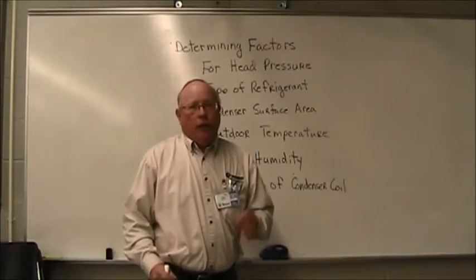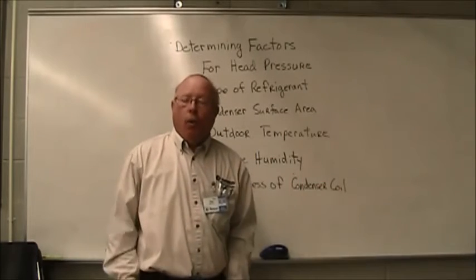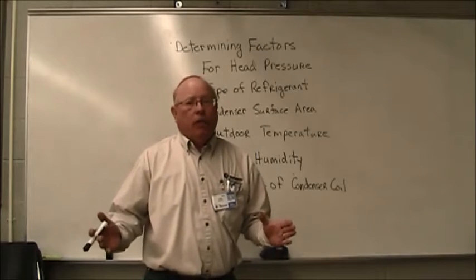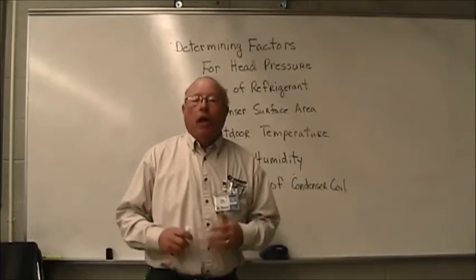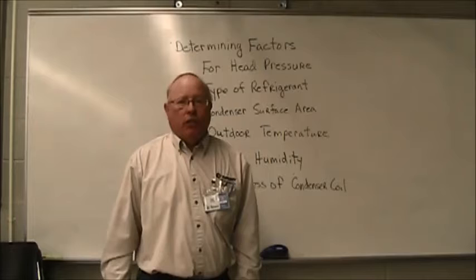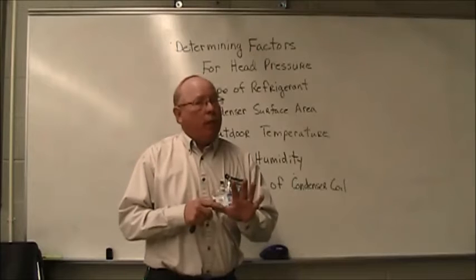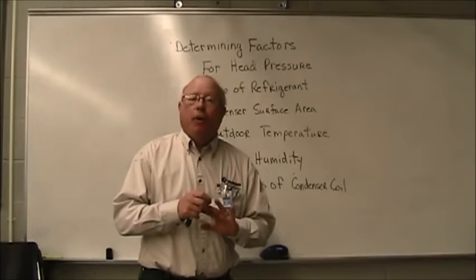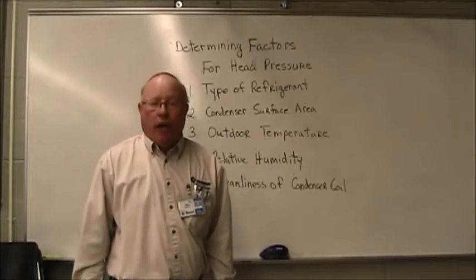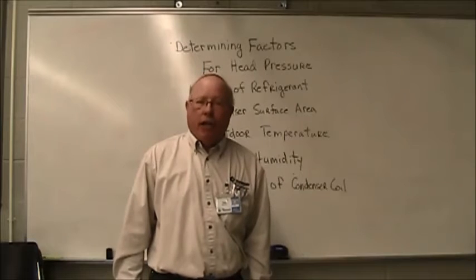Welcome to the 2 Minute Tutor. Today we're going to be looking at what are the determining factors that decide what my head pressure is going to be in a refrigeration system. This applies to all refrigeration systems, as long as they have the five things that make up any refrigeration system: a compressor, a condenser, an evaporator, a cooling medium, and a metering device. As long as it has those things, it's going to have a high side and a low side, and it's definitely going to have high pressure, or head pressure.